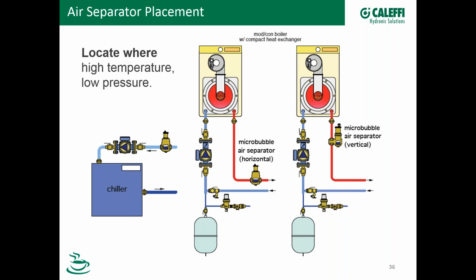So the answer is dependent on your application. By placing it up close to where you're starting to zone off, that would give you the advantage of both A, high temperature, and B, low pressure, which is the place you're trying to look for when determining the proper placement, or I should say optimal placement, for an air separator. Yep, exactly. Good point. And remember, if it's really difficult to locate it in one place, you can locate it in another place. Just try to follow the high temperature, low pressure rule as best you can. And remember, they're multi-pass devices, right? So maybe it'll take a little longer. If it's not in the absolutely perfect location, you'll still get effective air removal.